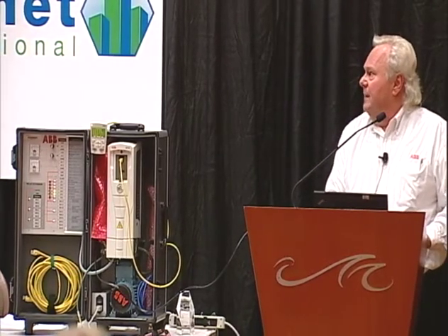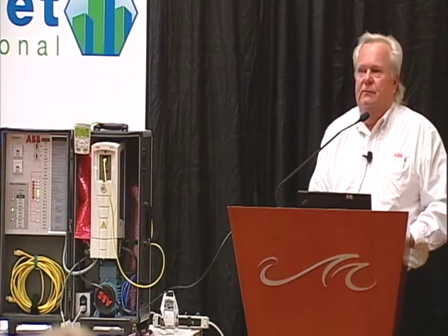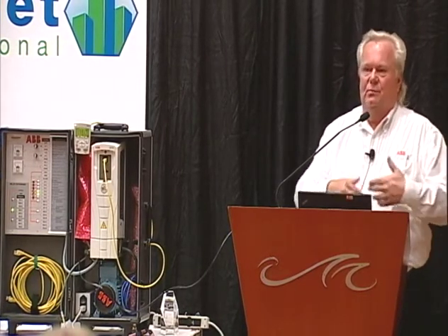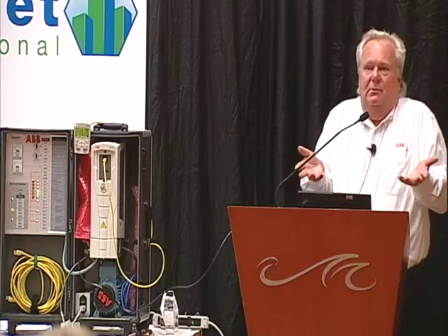Same thing, digital input 5. I can fire relays for whatever reason I want. We call it pass-through I/O. It's free relay outputs that are in the drive anyhow. You can use them if you want, don't use them if you don't, they're there. And we expose them across the BACnet system. The hot water valve here, we have two 4 to 20 milliamp or 0 to 20 milliamp analog outputs.